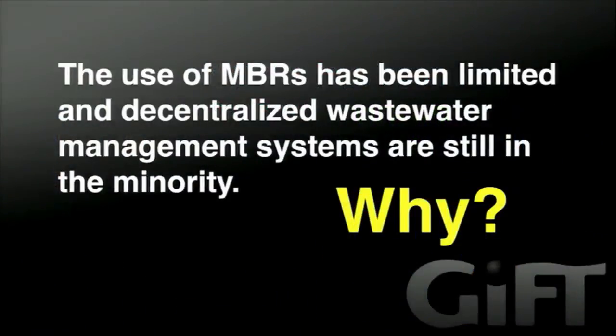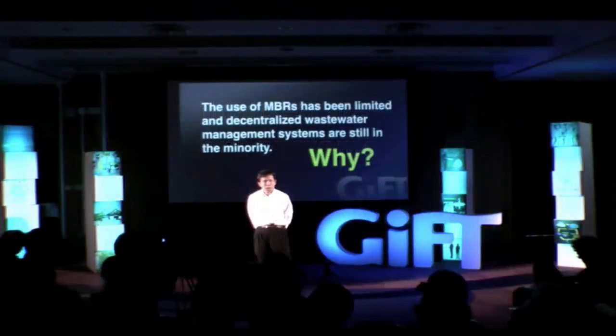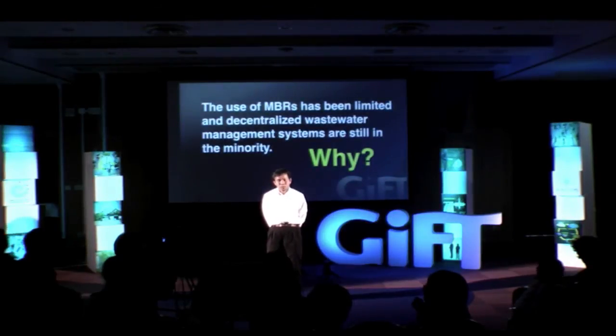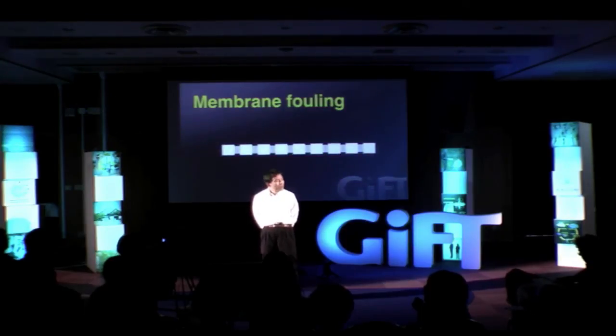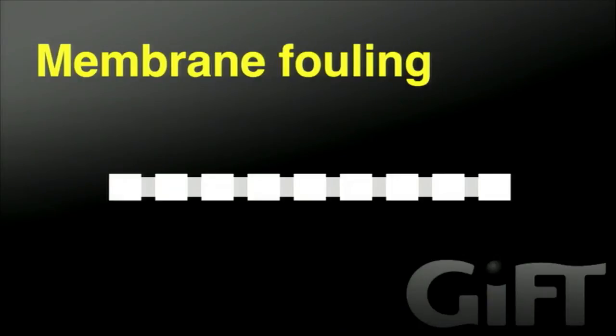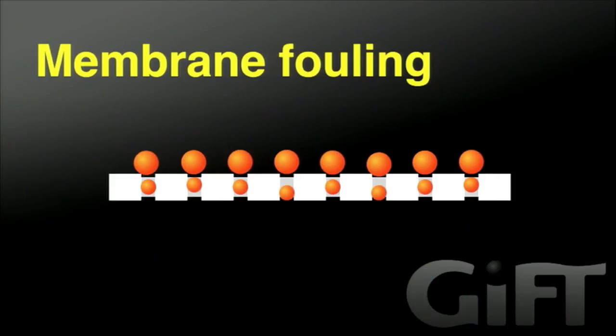In spite of the advantages I have described, the use of MBR has been still limited, and decentralized wastewater management systems are still in the minority. Why? There is a problem in this technology. In long-term operation of a membrane process including MBR, some components will accumulate on and in membranes and permeability will be reduced. This phenomenon is membrane fouling. Membrane fouling increases both operational and initial cost, limiting the wide application of membrane technology. So for widespread use of MBR, we need to address the problem caused by membrane fouling — and therefore, membrane fouling is a very important and hot research topic.